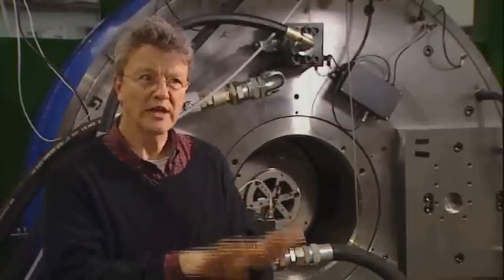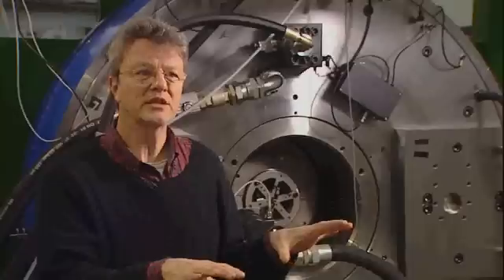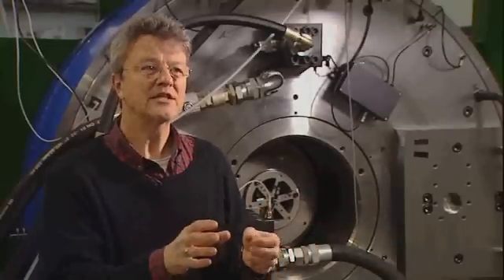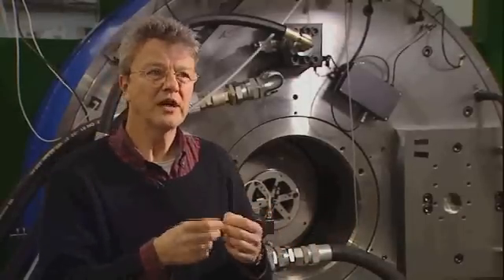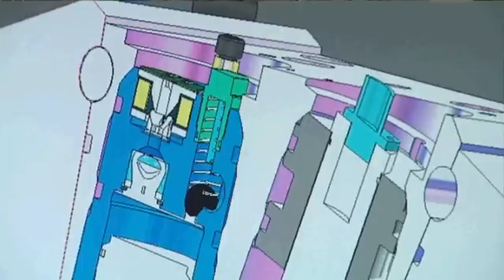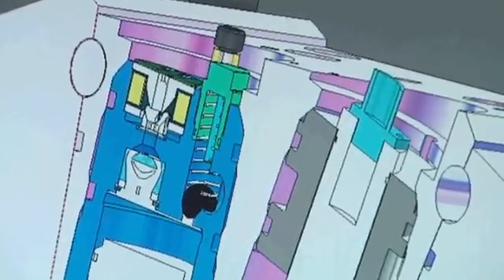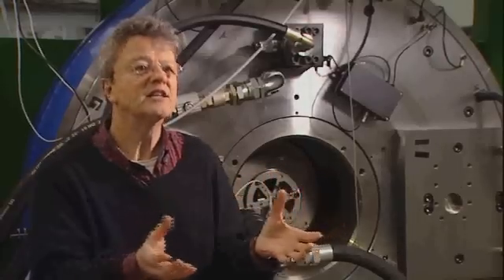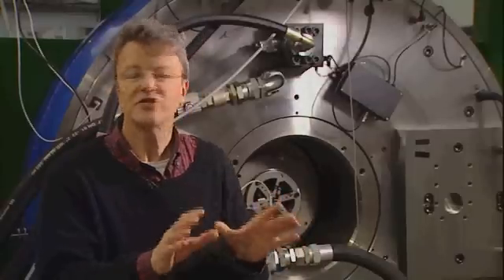Maybe we're working way down at part load, at 10% of the full rating. If that's the case, then the computer will automatically disable that cylinder by controlling the valve at just the right moment. It just returns the flow, the oil, back to the low pressure reservoir. And we call that idling. That's a really key part of it, because a cylinder that's idling has very, very low losses indeed. And that's a major contribution to the much higher part load efficiency.